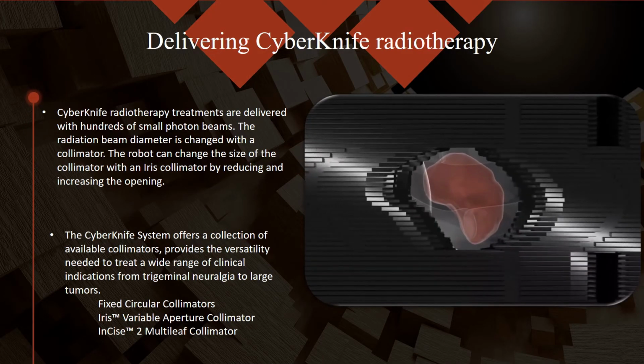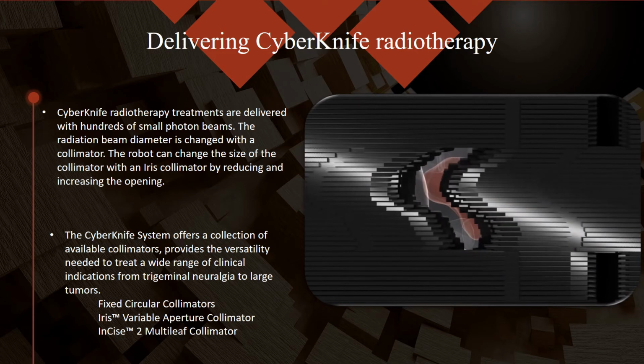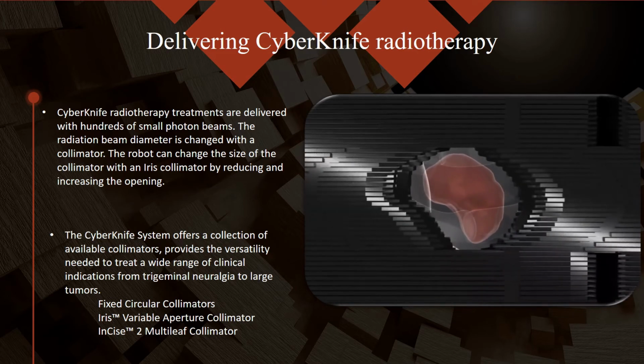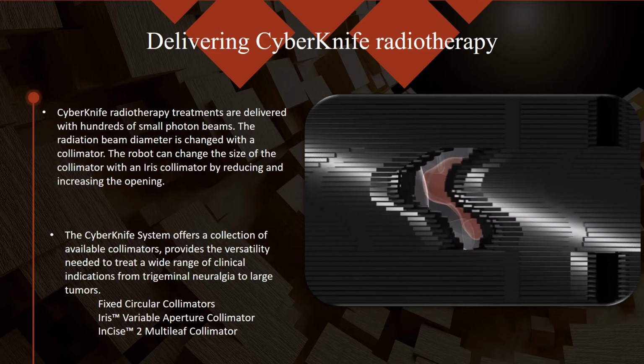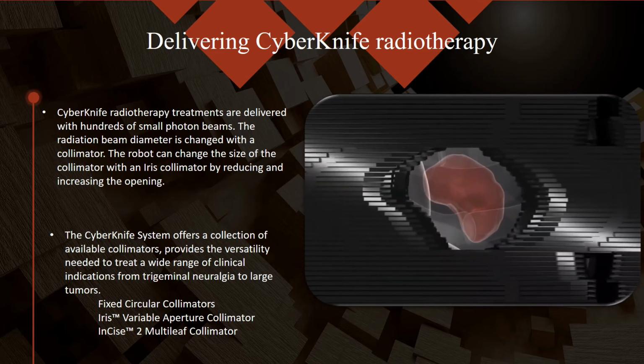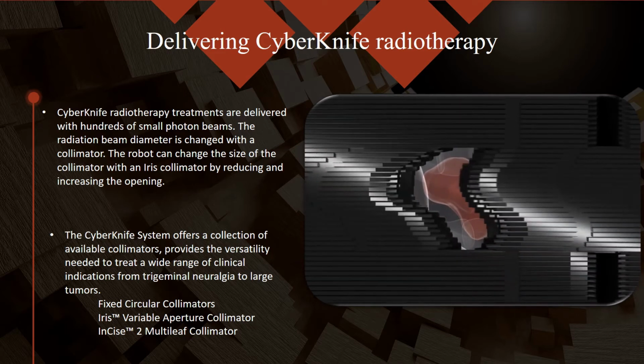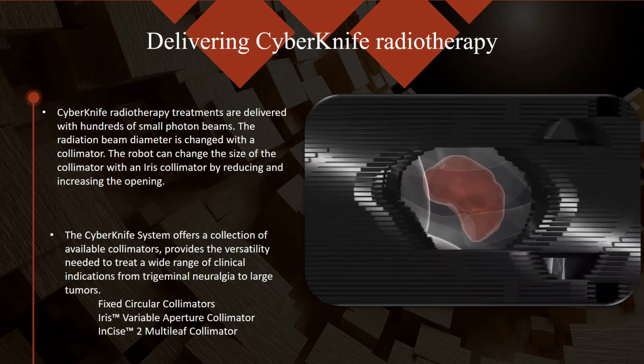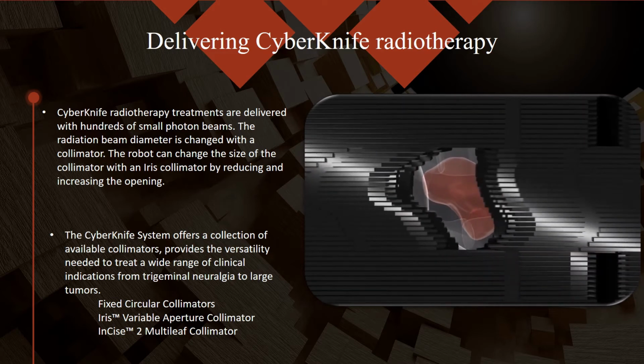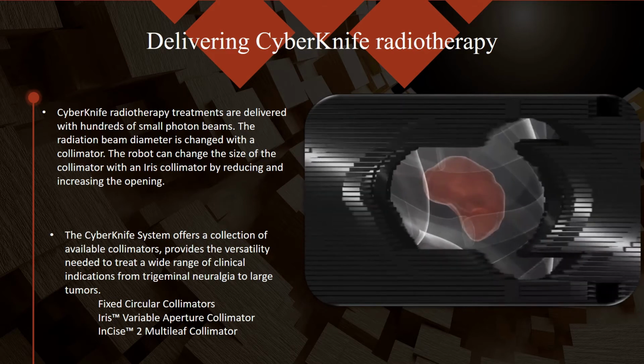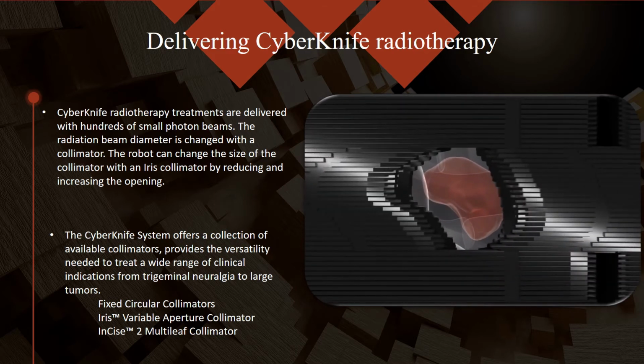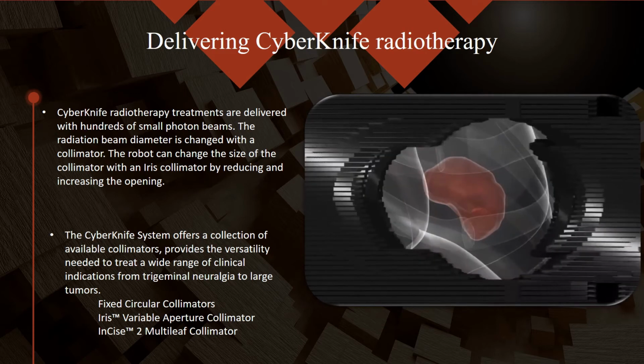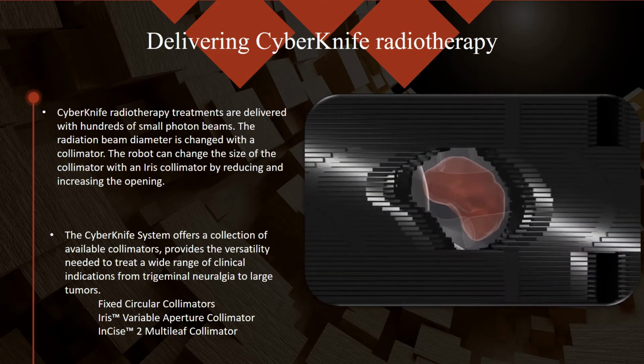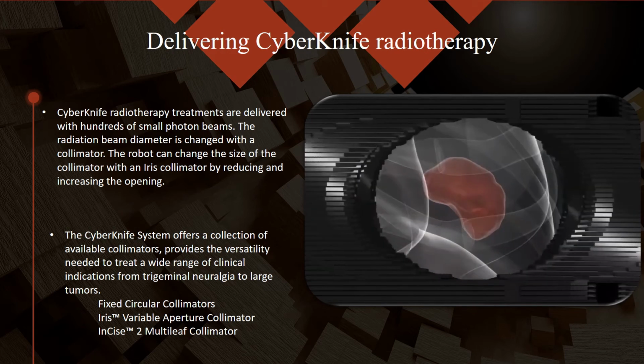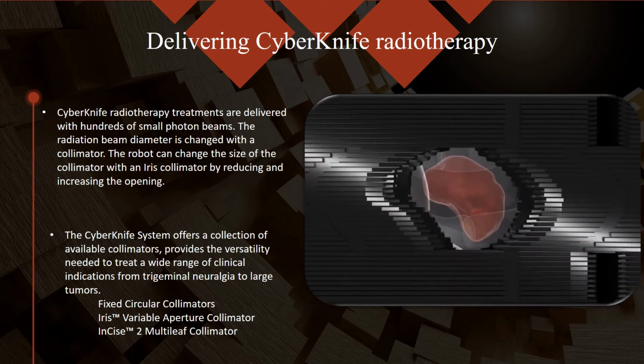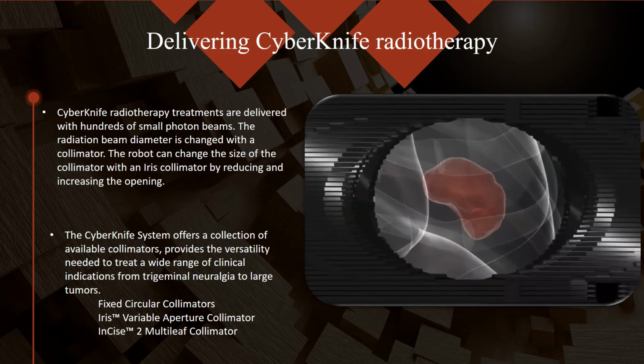Delivering Cyberknife radiotherapy. Cyberknife radiotherapy treatments are delivered with hundreds of small photon beams. The radiation beam diameter is changed with a collimator. The robot can change the size of the beam when fitted with an iris collimator by reducing and increasing the opening. With some treatments, only a few beam sizes are needed, so the iris is not needed. The robot can then pick up a suitable fixed collimator from the exchange table next to the robot. This is done automatically, even during the treatment.